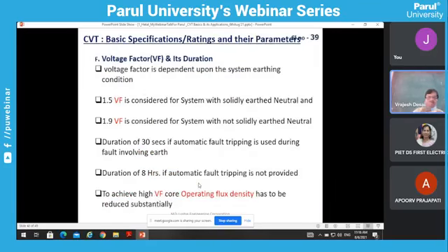Now coming to the voltage factor. What is the voltage factor? A voltage factor is nothing but the operating flux density with which the particular PT is designed. Normally a 1.5 voltage factor is there, and 1.9 is also there. With 1.9, when the neutral is not earthed properly, the secondary side voltage gets over-voltage by 1.9 times, right? And 1.5 times is always there even though the neutral is earthed. So you have to leave some space in the core design so that it does not get saturated, right?